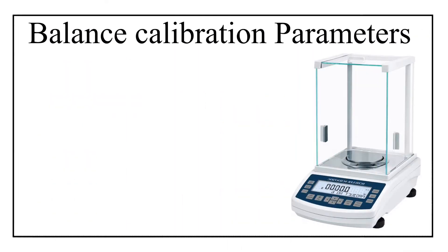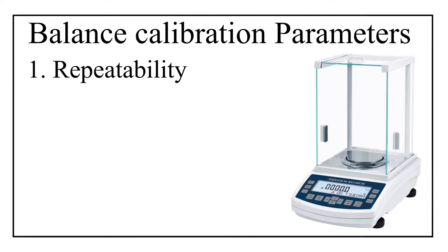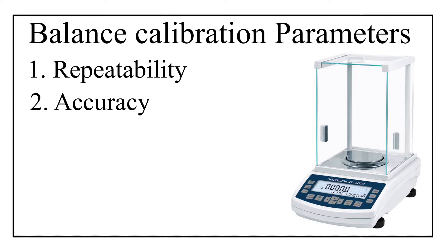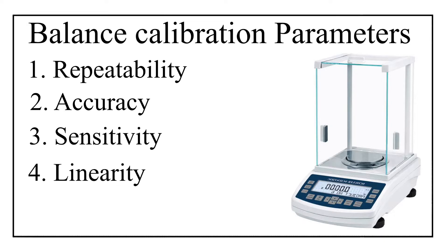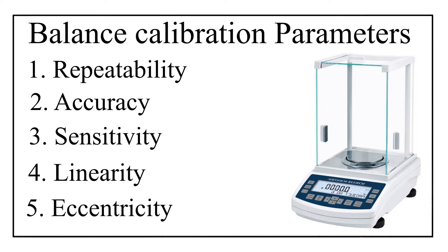A typical balance is calibrated with the help of five calibration parameters: number one, repeatability; number two, accuracy; number three, sensitivity; number four, linearity; and number five, eccentricity. These are the five main calibration parameters of a balance, which are used globally by all pharma companies.